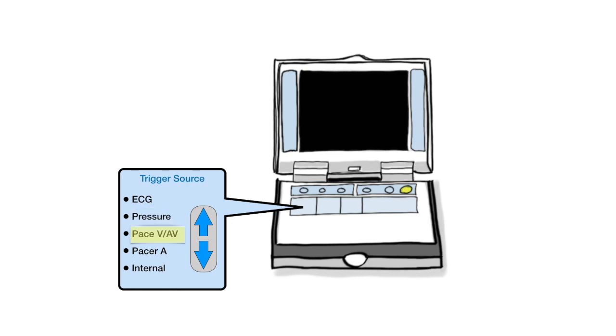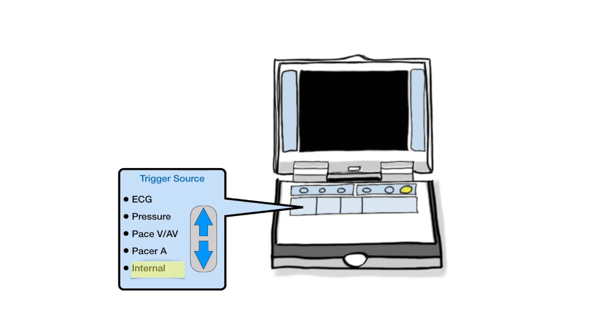Pacer VAV uses the ventricular pacer spike in V or AV paced rhythms to deflate the balloon. Remember, when 100% paced, there is no reliable R-wave. Pacer A uses the R-wave to trigger deflation. Internal defaults balloon inflation to 80 beats per minute and is used only during cardiac arrest, never used in a patient generating their own cardiac output.